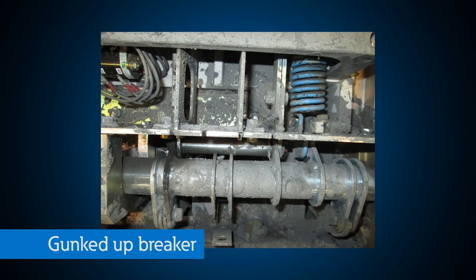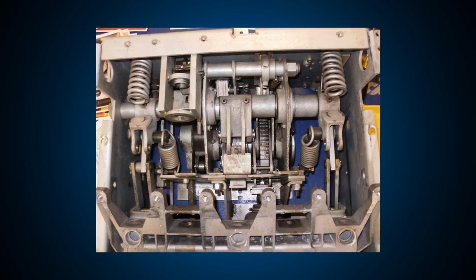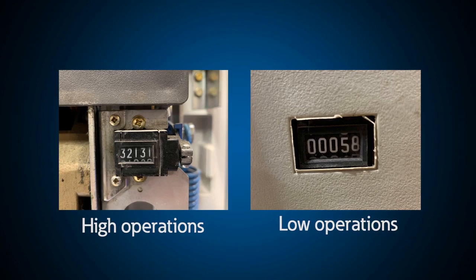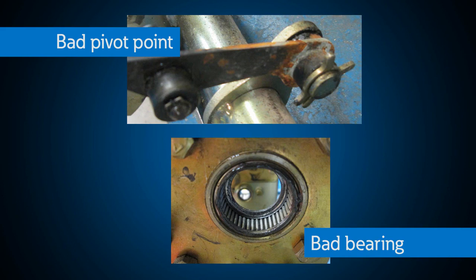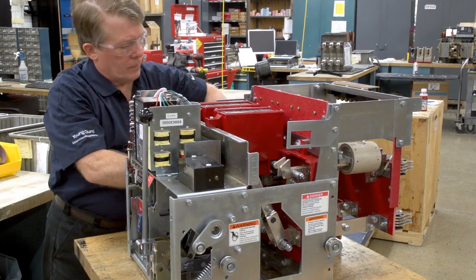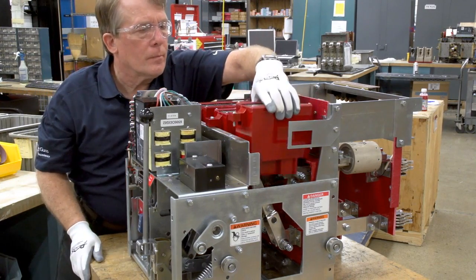If the lubrication of electrical equipment is not maintained, it can cause equipment to misoperate or not function when needed. This is generally a major problem with power circuit breakers since they have many mechanical parts that need to move freely. Whether a circuit breaker has a high number of operations or very few operations, it can be problematic. A high number of operations can result in excessive wear to mechanical components. A very low number of operations can result in the hardening of certain types of lubrication on pivot points as well as bearings. With thorough inspection and proper preventative maintenance, electrical equipment has a much greater chance of operating correctly.